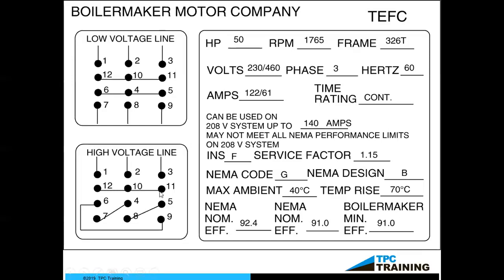The next thing we see is a NEMA code G, and I would have to get into Article 430 of the National Electrical Code. There's a table in that article about locked rotor, and what that table tells us for the letter G, there would be a number in there, and that number, let's say, could be the number 5. Well, if that shaft or that rotor froze and would not turn, it's going to give us an idea how much current would flow. So you take 5 times, let's say, the lower amps, because we're on the higher voltage, so 5 times 61, that motor is going to draw about 300 amps, either on startup when it's not turning at all, or if the rotor freezes up on us.